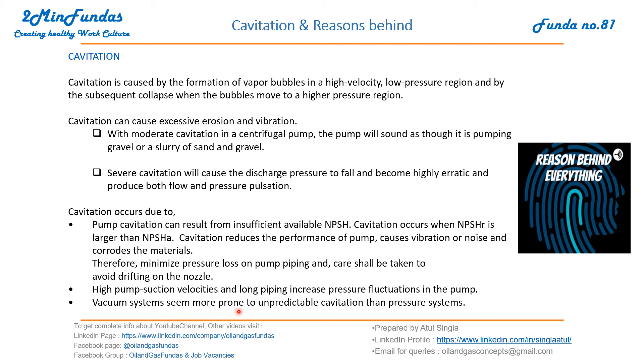Vacuum systems seem more prone to unpredictable cavitation than pressure systems — cavitation is more commonly found in vacuum systems. So, to summarize: cavitation occurs due to bubble formation in low pressure regions, and we can avoid it by minimizing the suction length. That's why we go for a straight length in pump suction lines, which will be discussed in coming slides.